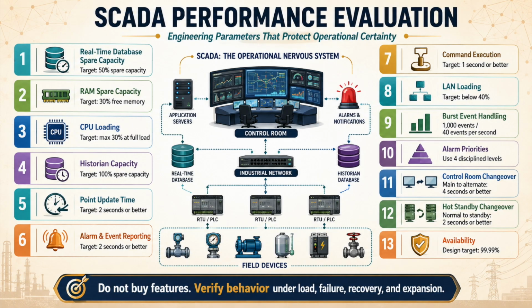The 15th engineering parameter is main control room to alternate control room changeover, because this is not only redundancy testing, it is business continuity and command authority testing. A 4-second or better changeover target may be required where operations depend on alternate control centers, and operators must know which control room is active, which is standby, whether commands are enabled, whether alarms are synchronized, and whether values are live. Poor control room changeover creates stale displays, duplicate alarms, missing acknowledgements, uncertain command authority, and confusion over who is actually controlling the asset. So engineers must test main control room failure, network isolation, server failure, client failure, command continuity, alarm state, active standby indication, and recovery behavior.